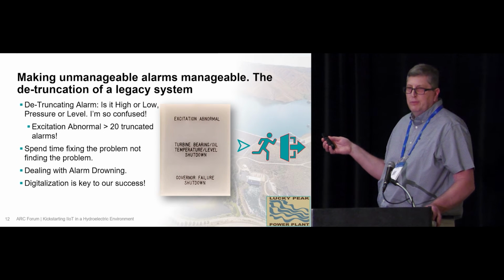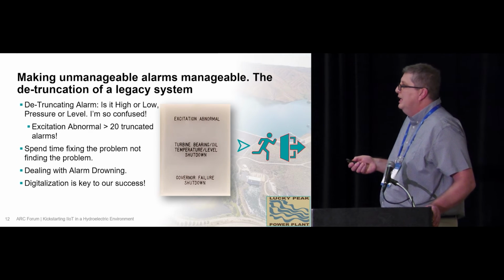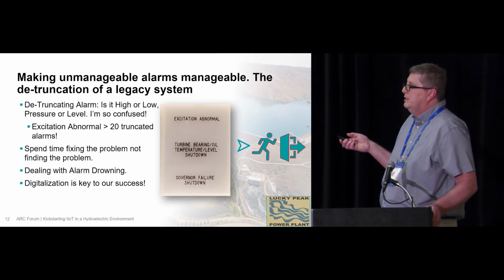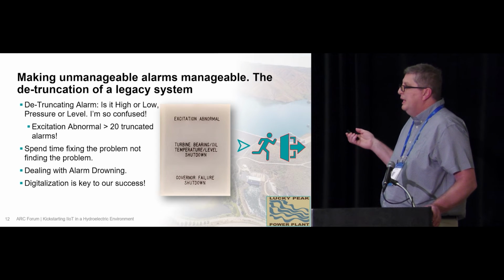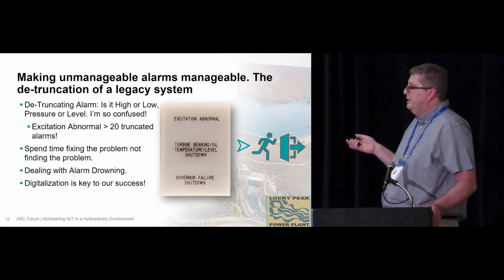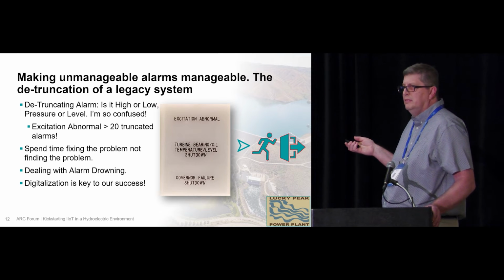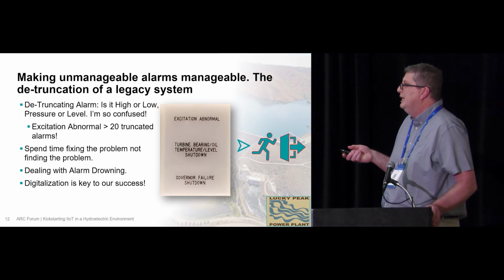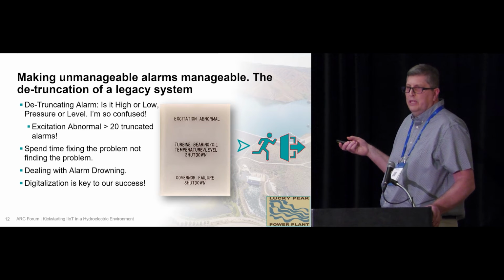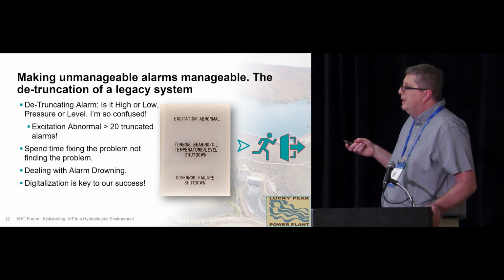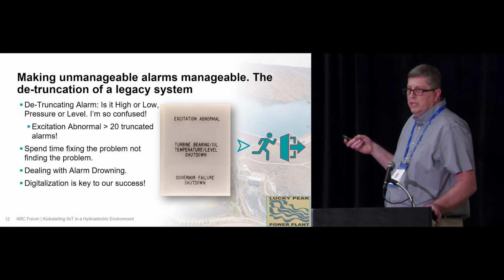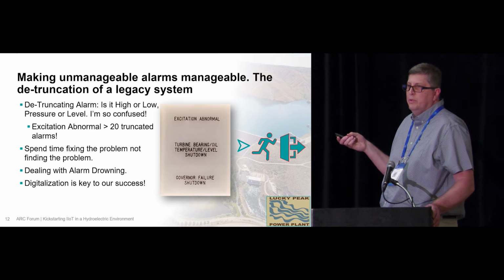Back to alarming real quick, since it's a passion of mine. Here's an example of what we were dealing with. In the middle we have a turbine bearing oil temperature level alarm. Sure, but I'm not sure what I'm supposed to go look at with that—levels or temperatures? Along with our excitation abnormal alarm, we had 20 different alarms that could come in, and they'd just light up that one box telling you there's an issue.